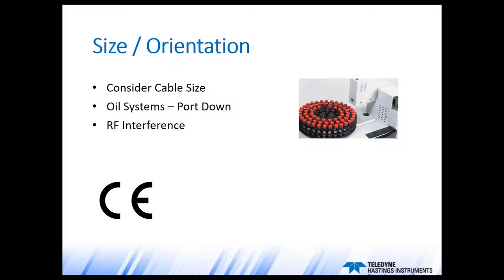Consider the size and installation of the vacuum gauge. Most companies provide outline drawings and step files to help with system design. When packaging analytical instrumentation, size can be very critical — not just for the gauge, but also for the cabling. If working with an oil-based pump, ideally you want the port of the gauge facing down. If designing for CE approval, you need to think about RF interference, as the installation location inside a chassis can have a large effect on the gauge's susceptibility to RF interference.